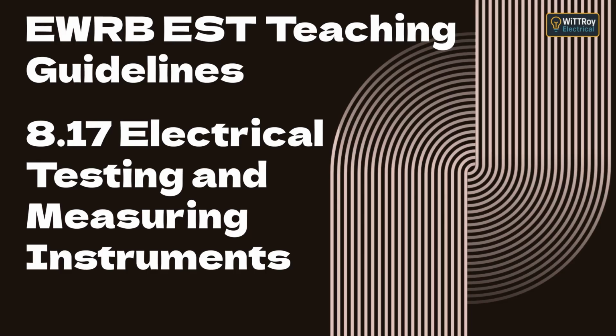Topic G. Interpreting test readings. Now let's talk about Topic G. Testing isn't just about recording numbers, it's about knowing what they mean. If you measure high resistance on a continuity test, that suggests a loose connection or corrosion. If you measure low insulation resistance, that indicates moisture, damaged insulation, or contamination.